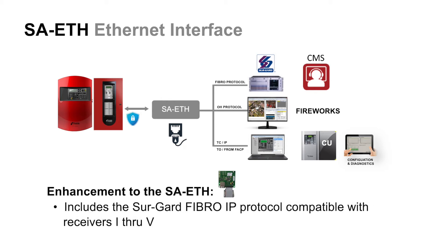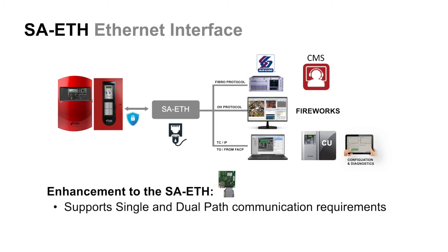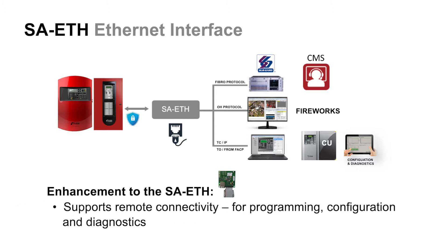The enhancements include the Sur-Gard Fibro IP protocol, which makes our system compatible with receivers from Sur-Gard, like the Sur-Gard 1 through 5. It supports single and dual-path communication requirements, and currently supports the connection to our Fireworks workstation. It supports remote connectivity for programming, configuration, and diagnostics — but keep in mind that if any program changes are performed remotely, a technician needs to be on site to perform local testing of any changes made to the system.